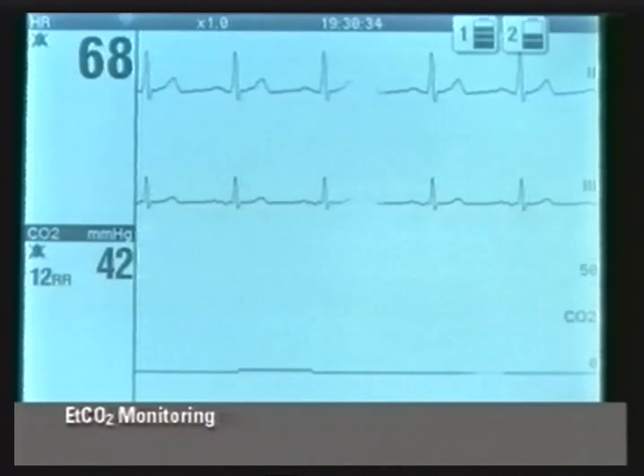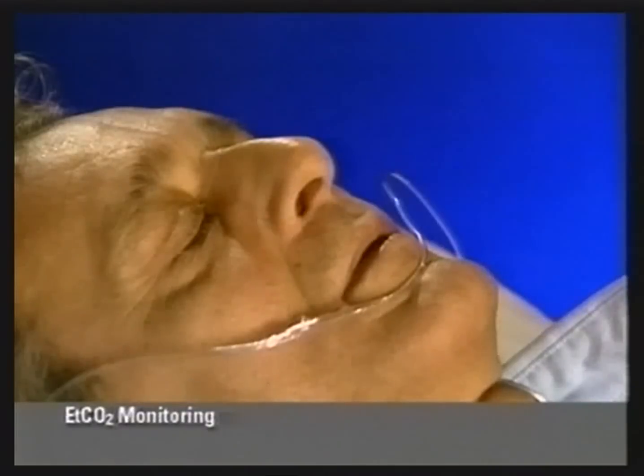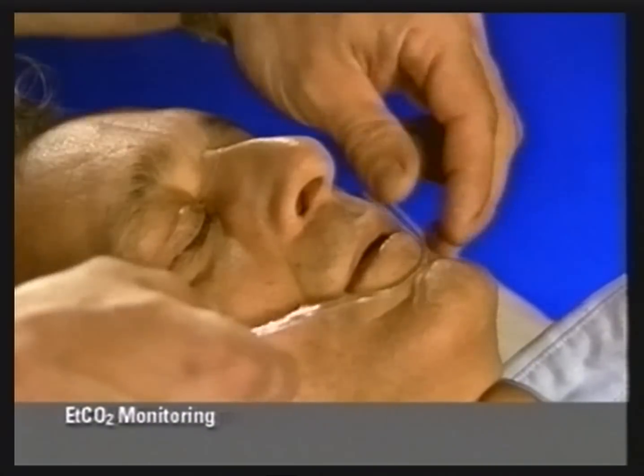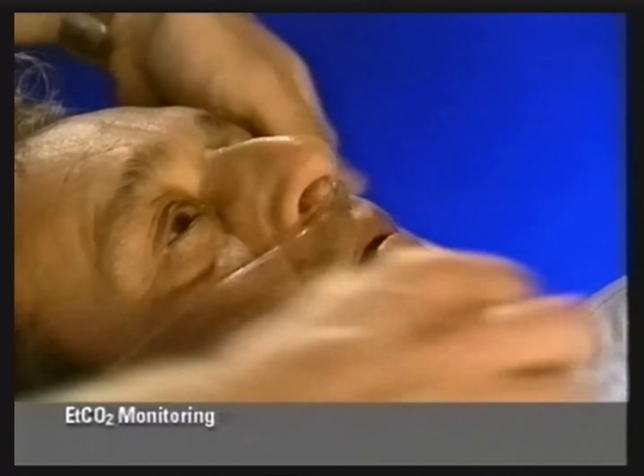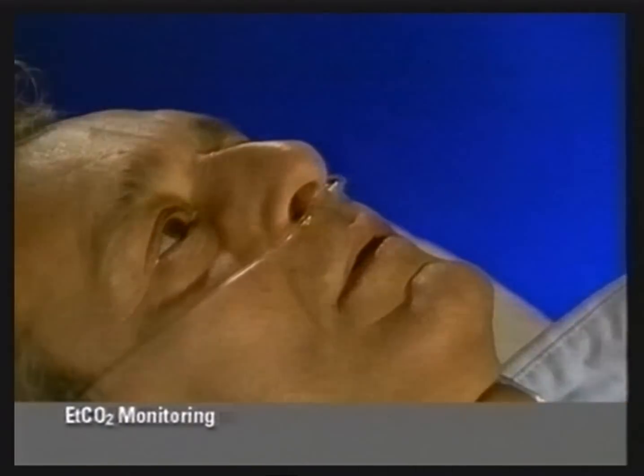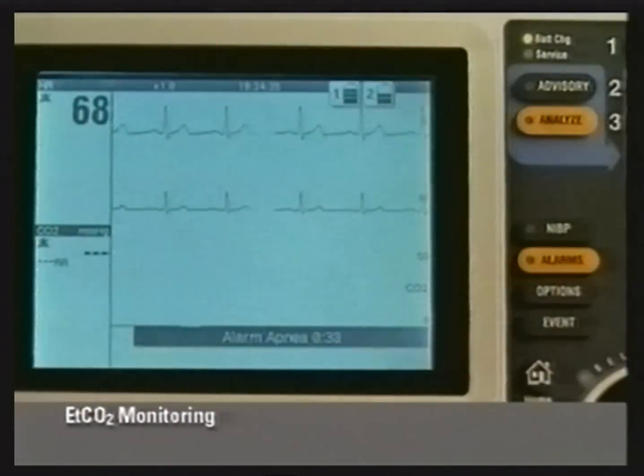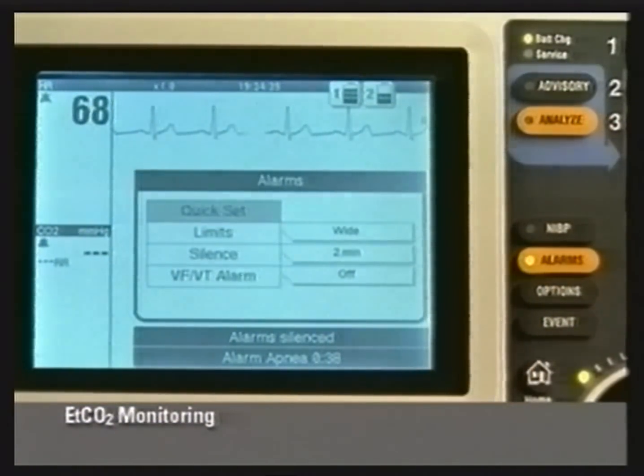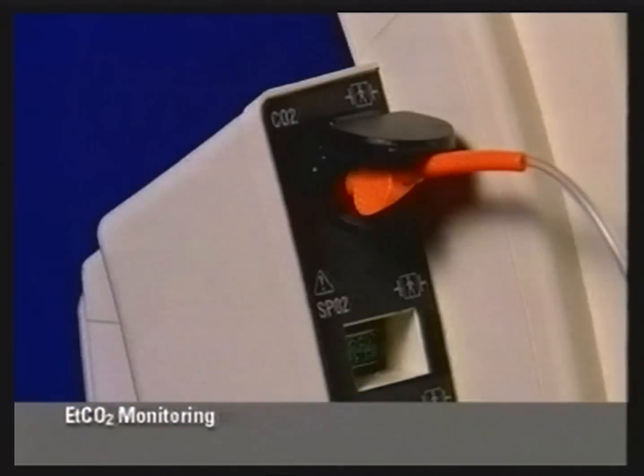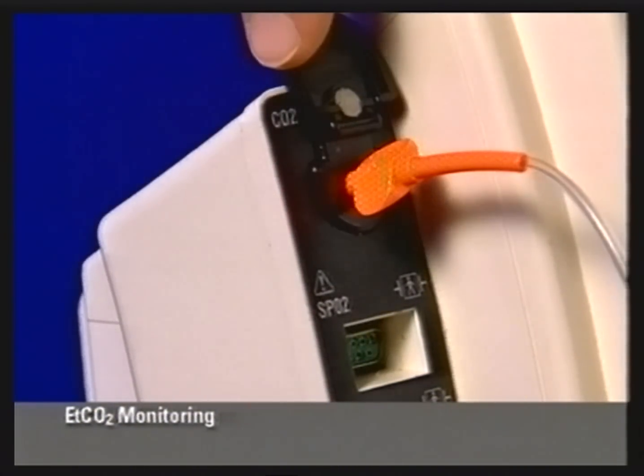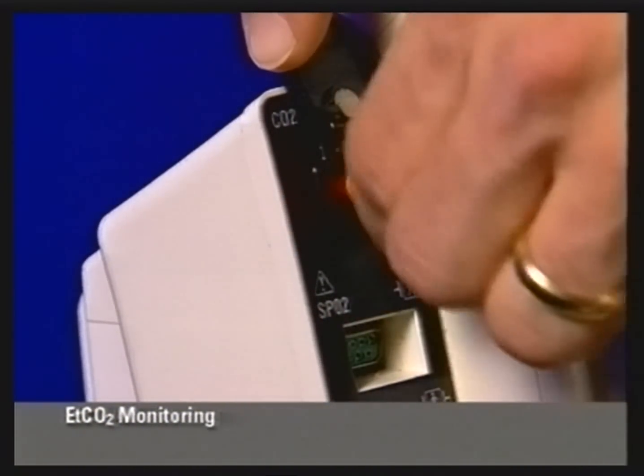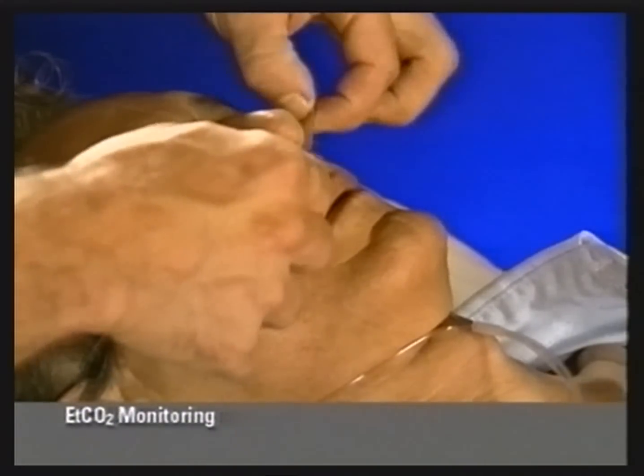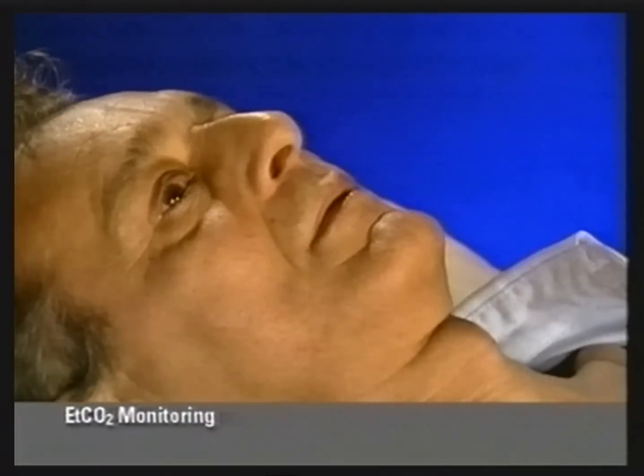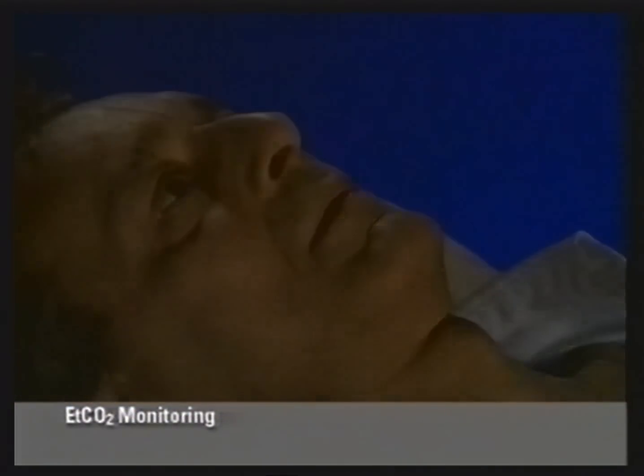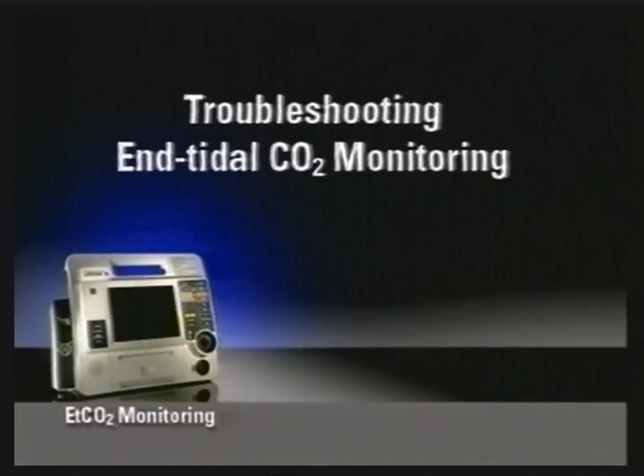If an apnea alarm occurs, first check the patient and then the tubing to see if it has been dislodged or disconnected. The alarms can be temporarily silenced by pressing Alarms. When CO2 monitoring is no longer desired, disconnect the filter line from the device. This removes any CO2 alarm condition and reduces the power drain on the battery from the CO2 module.